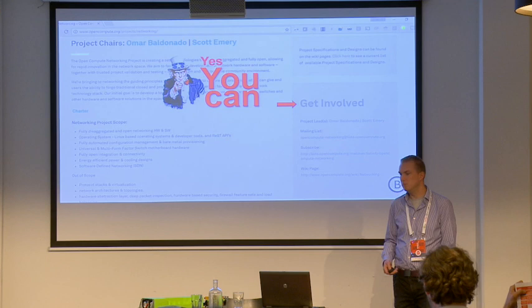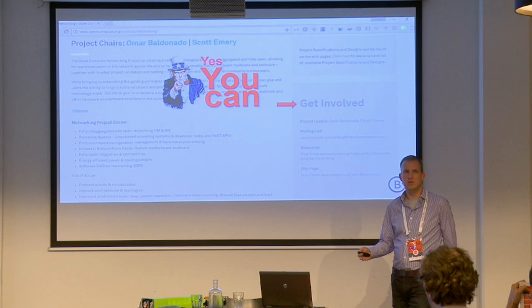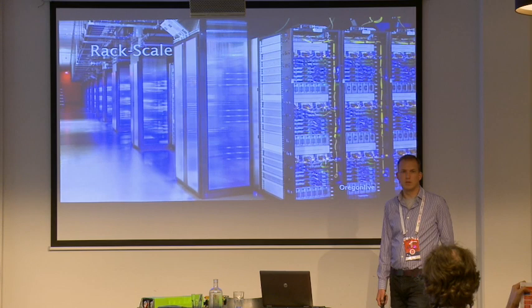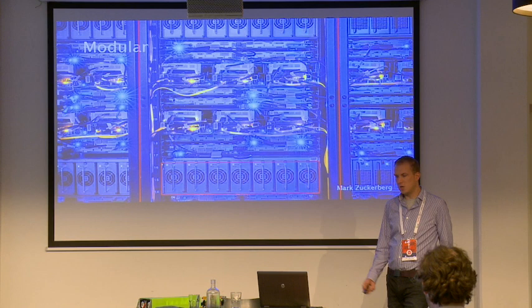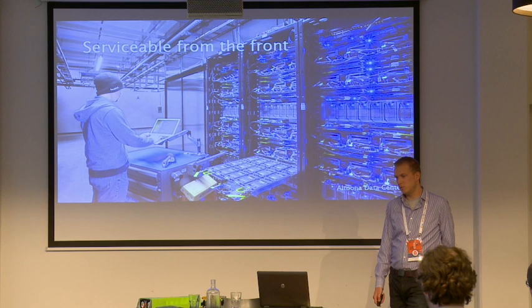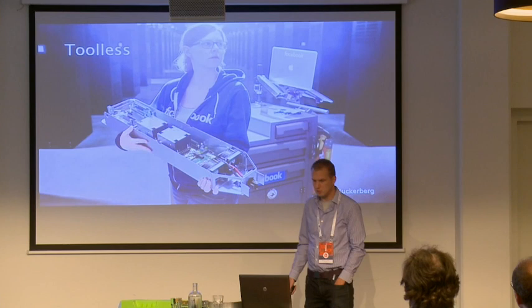The idea is that you have one design and there are multiple manufacturers — you can multi-source the same design. It's a rack-scale architecture. You need to begin with one whole rack and then expand — it's limitless. It's a modular design. The biggest module we deliver is the rack with the power shelf and power supplies inside, then the servers and storage. It's all serviceable from the front of the rack — you don't need to be in the hot aisle behind the rack. It's a tool-less design, and all the green touch points are at the front. You don't need any tools for maintenance.